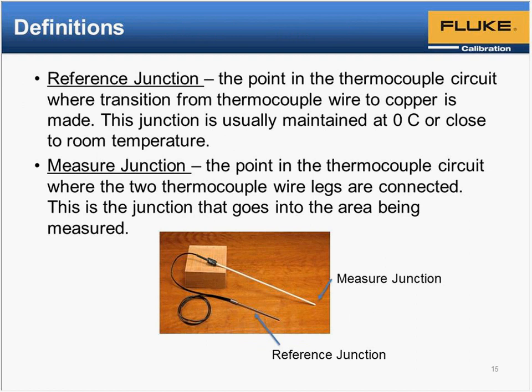Okay, so just one more quick thing about these two junctions, just to really nail it down. The reference junction is the thermocouple circuit where the transition from thermocouple wire to copper is made, and is usually maintained at 0 degrees C or close to room temperature. The measuring junction is the thermocouple circuit where the two thermocouple wires or legs are connected. Basically it just completes the circuit, allows us to see a voltage potential, and is the junction that goes into the area being measured. And we have a picture of a typical reference level thermocouple, and where the junctions are.